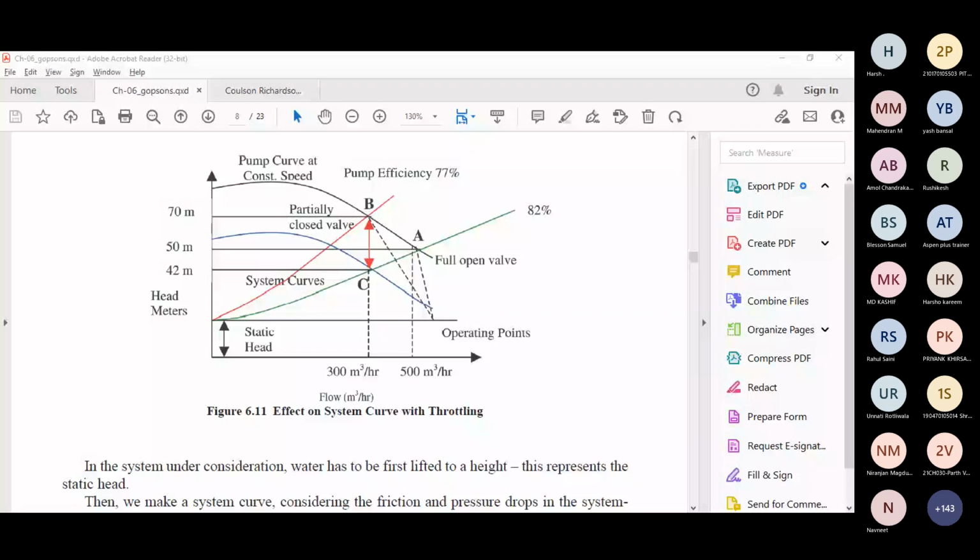So as such, pump में कुछ problem नहीं आएगा on longer period, but basically your power losses, your pump will not be operating at the BEP. So basically आपको क्या करना है? जब भी whenever you are designing, make sure that your pump should always operate near BEP. If it is deviating, basically, it will lead to more power losses.